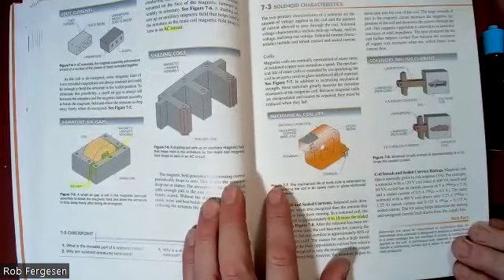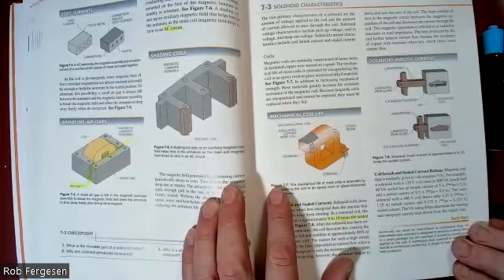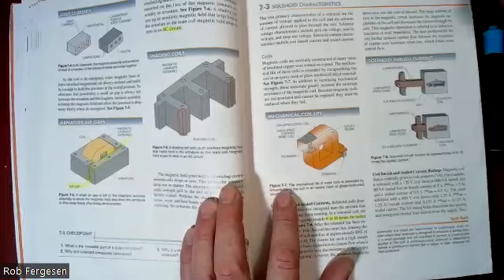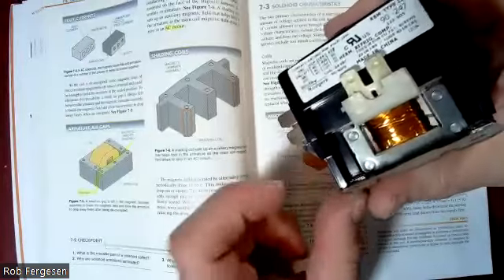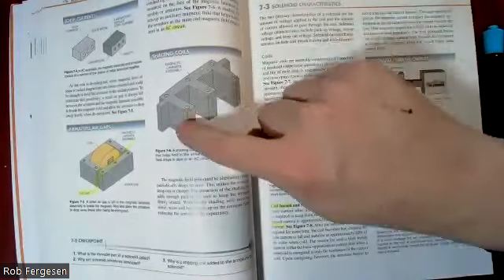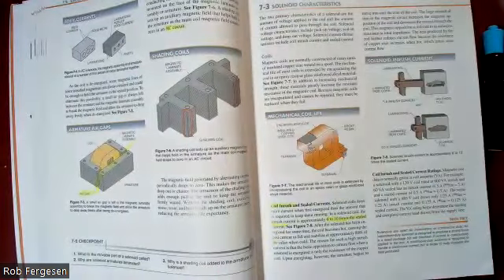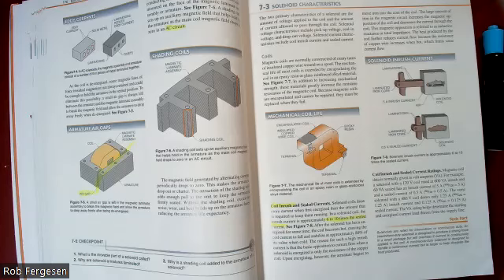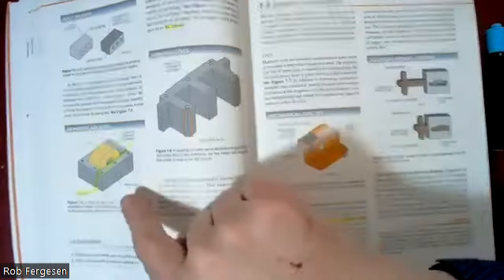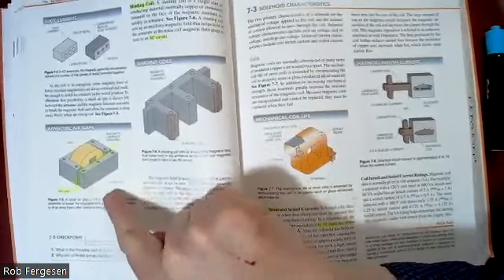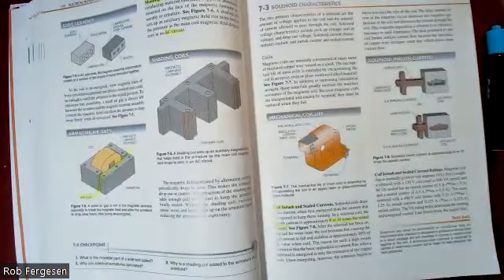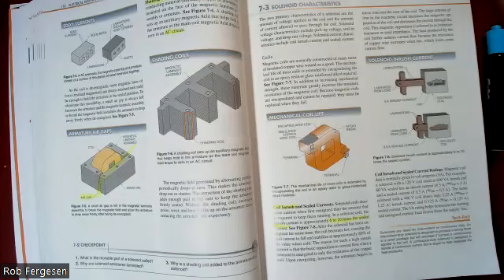What happens: an AC solenoid's magnetic assembly and armature consists of a number of thin pieces. If you look in here, what you see the edge of is many thin plates all screwed together. So there's two key aspects to how this works. Number one, you've got eddy currents that are created in that steel. Number two, you have to have an air gap that's critical to making it work properly. And if you have dirt or whatever causing a problem with the air gap, it'll slow it down or even make it not work anymore.